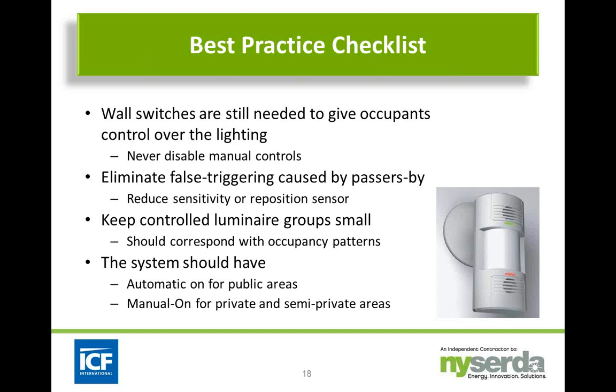You want to make sure you're eliminating false triggering caused by passersby, to reduce sensitivity and reposition the sensor appropriately. We've also talked about some masking features that you might be able to use. We'll talk about that in a couple of moments. You want to keep the controlled luminaires in small groups. If you have one large open office area that has 50 different luminaires in it, you don't necessarily need to have all those fixtures coming on at the same time. So you can break that down into smaller zones that are more appropriate to the activity within the space.